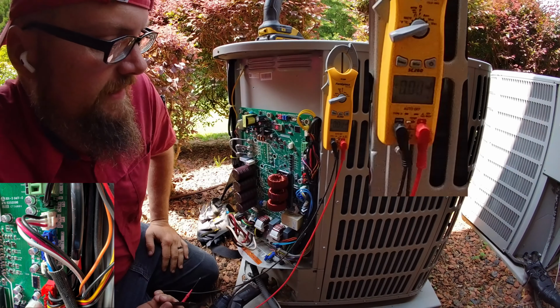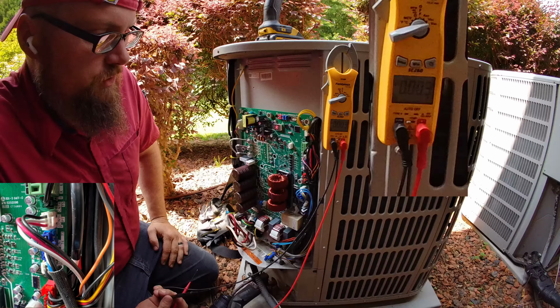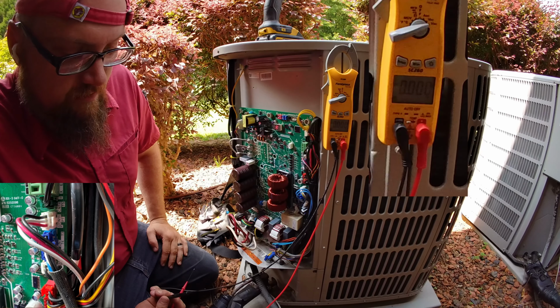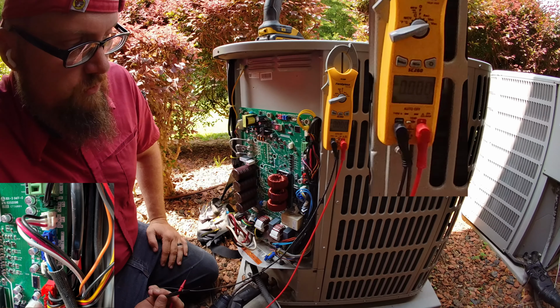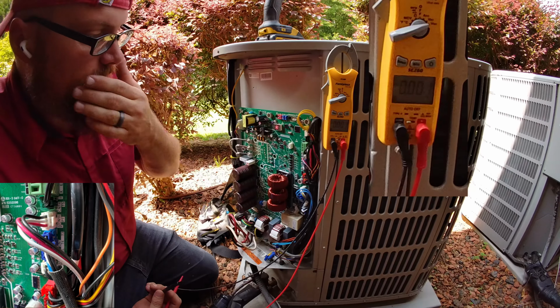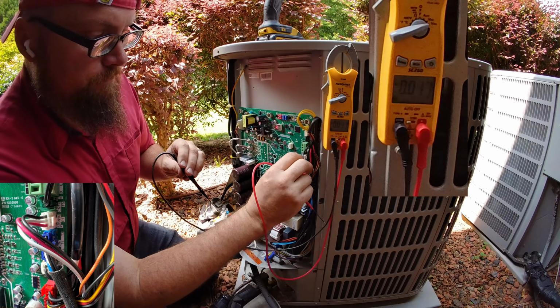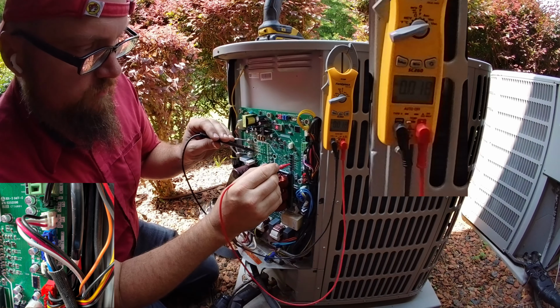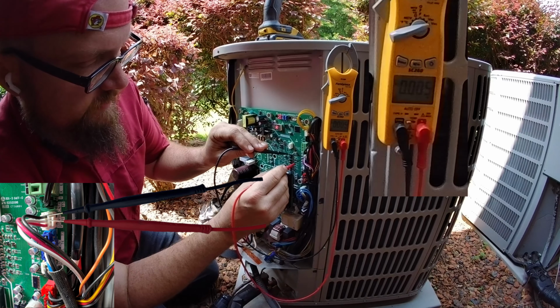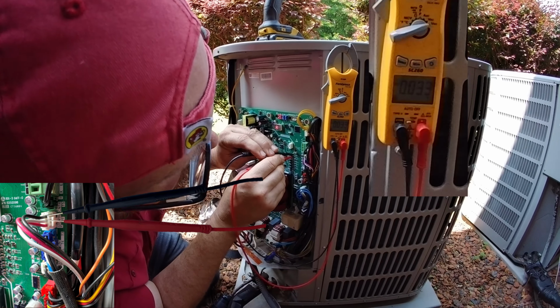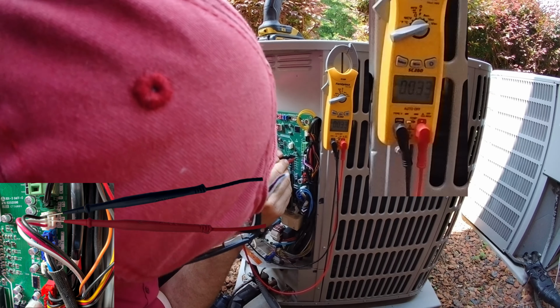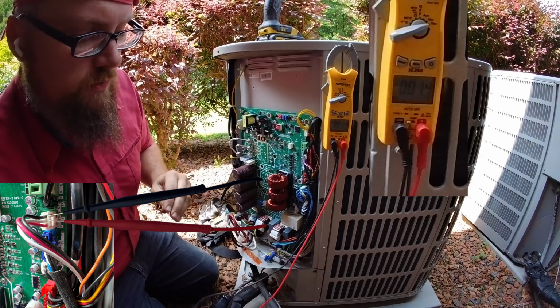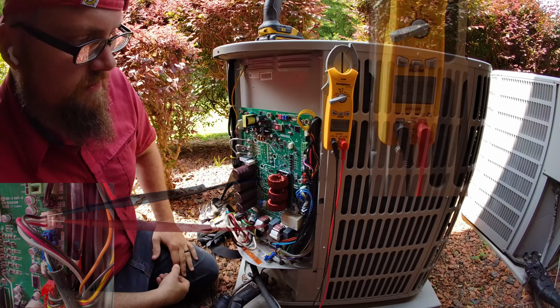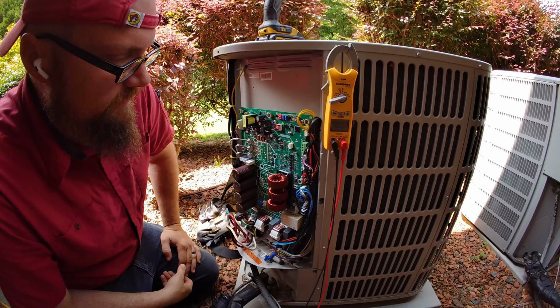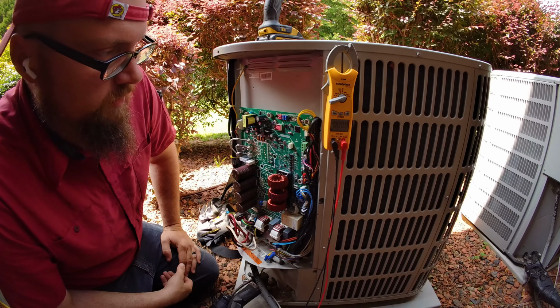So if we weren't seeing that, that would tell us we had a board issue. Since we are, that tells us we have an issue with possibly the transducer itself. So the way we check that is we go back between the white and black wires here, and you'll see we're showing 0.03, which honestly, that would tell me that more than likely we're out of range.